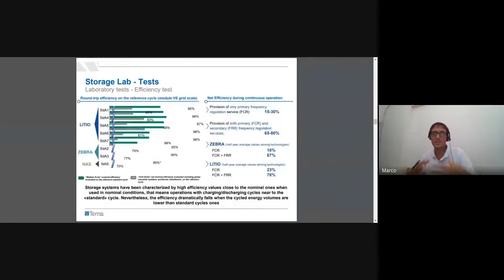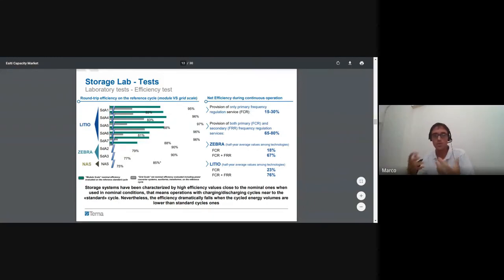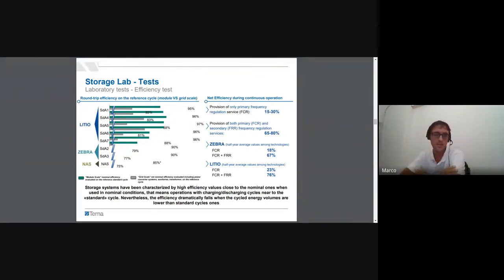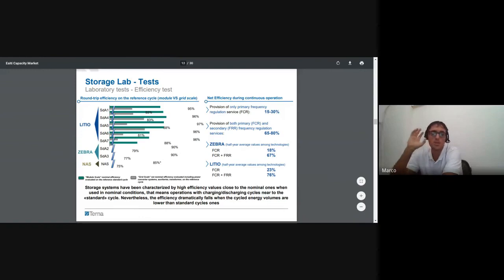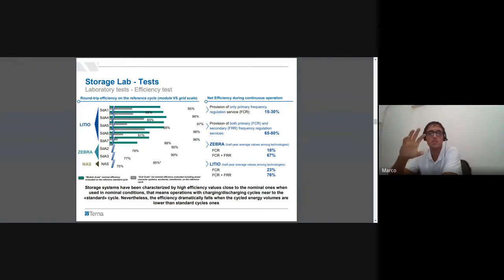Next, please. These are just a few results we've obtained, not the whole result, just a few screenshots, let's say. Here I'd like to share the testing we made on energy efficiency, the net efficiency of the energy storage system. Usually an energy storage system has a module efficiency higher than 95%. If you're talking about the whole solution with inverter, auxiliary services, and so on, this level usually stays around 85%. But the real question is: what's the real efficiency value in the life, in the operating condition?